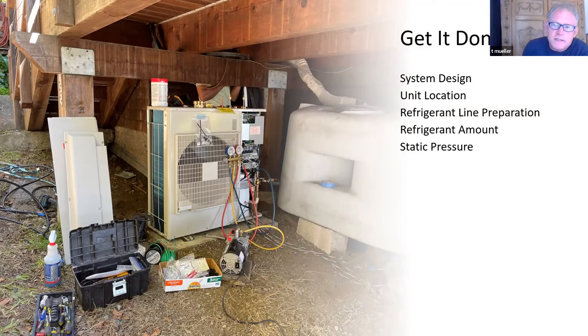And then finally, static pressure, which is the pressure across the system at the air coil inside. There's a cold air return side of the system and a supply side. You want the static pressure to fall within the manufacturer's specifications, or the system's just going to work too hard and not be as efficient.